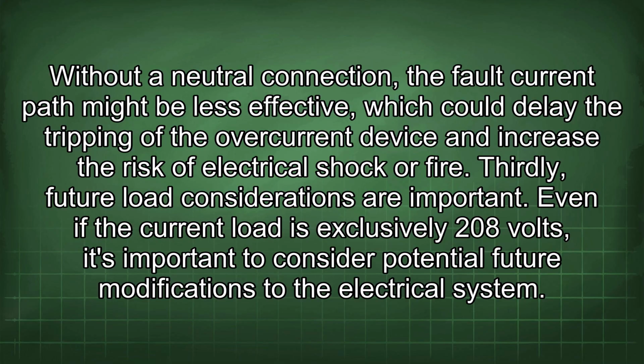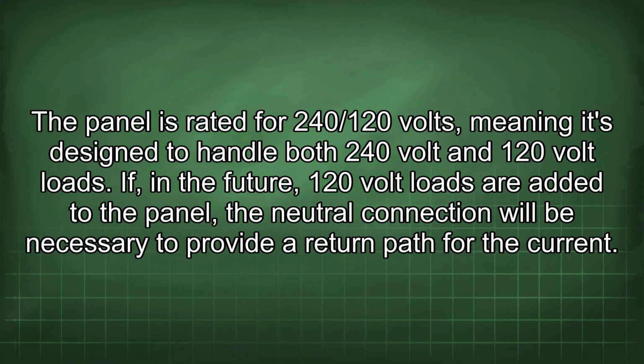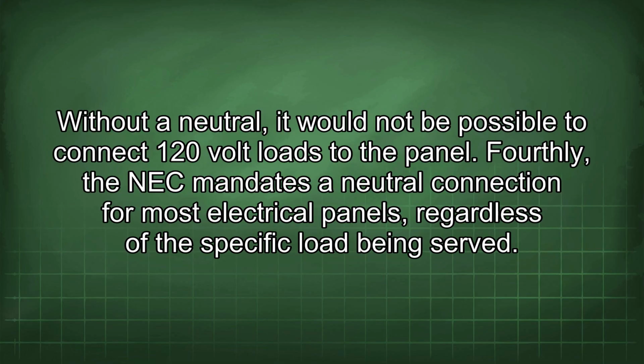Thirdly, future load considerations are important. Even if the current load is exclusively 208 volts, it's important to consider potential future modifications to the electrical system. The panel is rated for 240/120 volts, meaning it's designed to handle both 240 volt and 120 volt loads. If, in the future, 120 volt loads are added to the panel, the neutral connection will be necessary to provide a return path for the current. Without a neutral, it would not be possible to connect 120 volt loads to the panel.